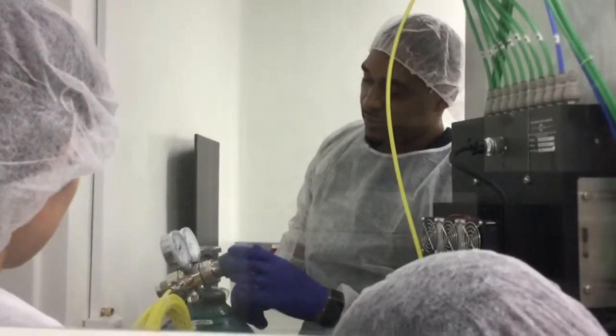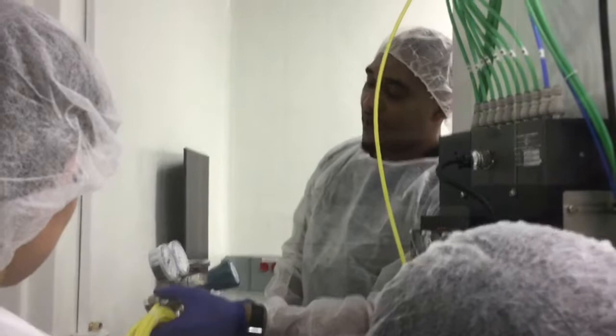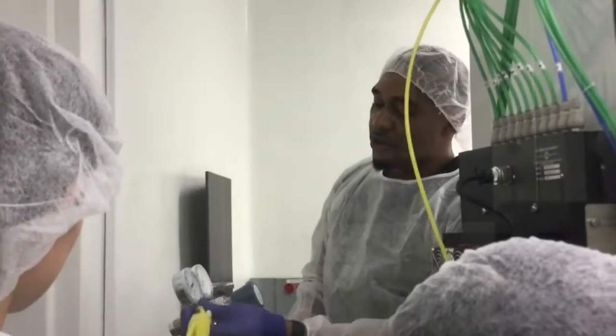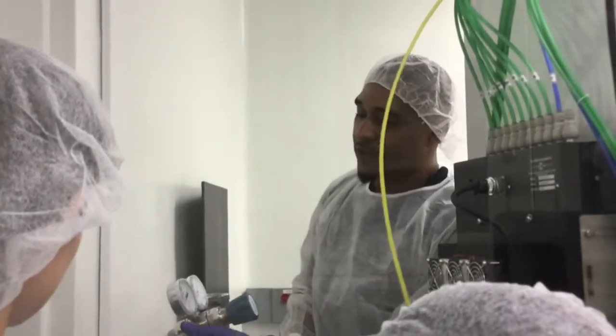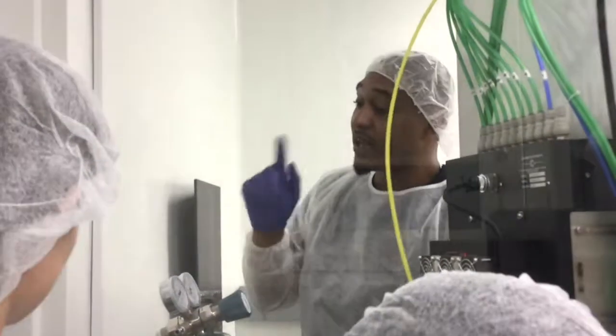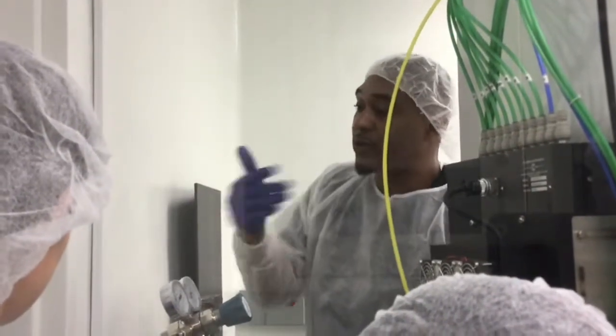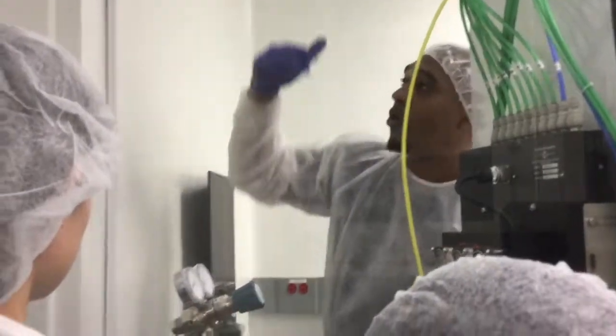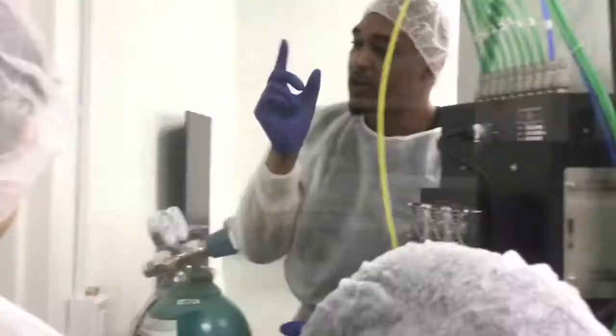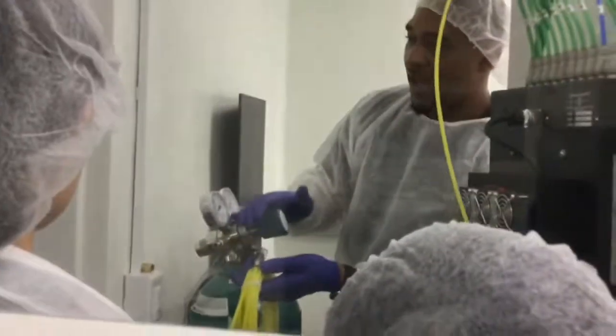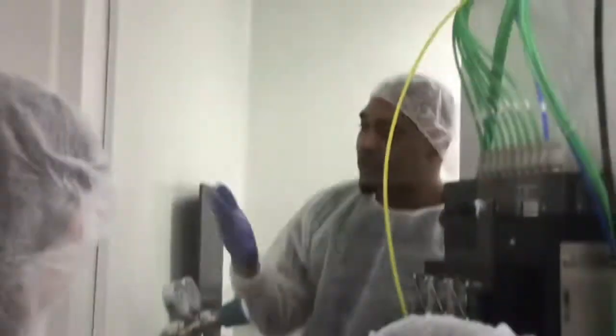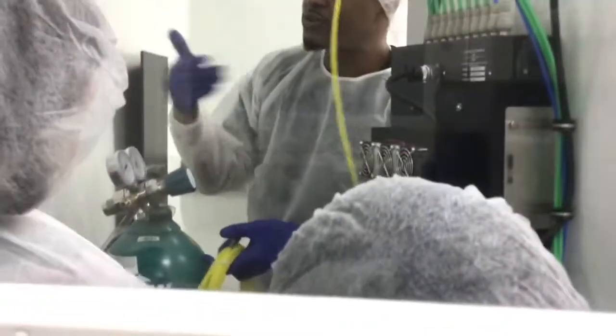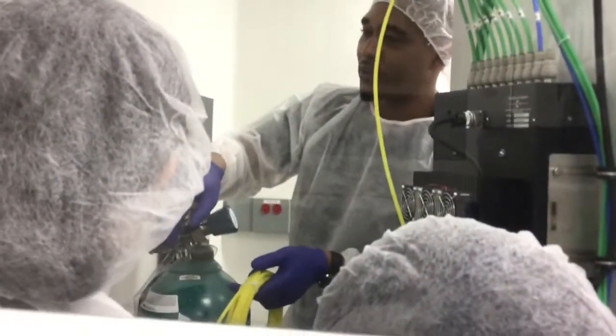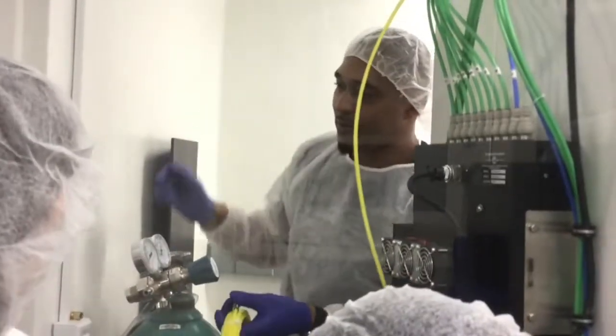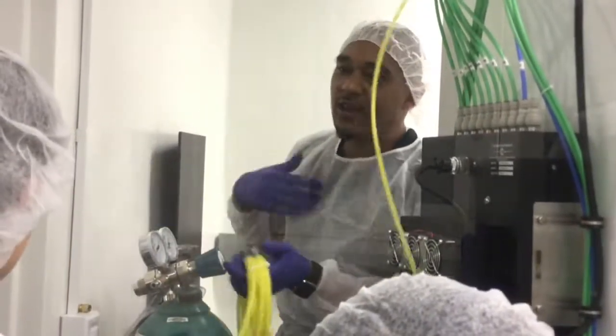Yeah, so again, it's pretty easy to push. Let me put this around 10. In fact, I'm telling you guys to unplug it, but you don't necessarily have to. If you forget, that's okay. But there's a lot of systems, our older systems, where you have to. On this one, which is pretty new, we found a way to just open the valve, suck some air from this, and close the valve. But it's just good not to leave anything plugged in on the gas, especially if you work with all the systems around. I just like unplugging it.